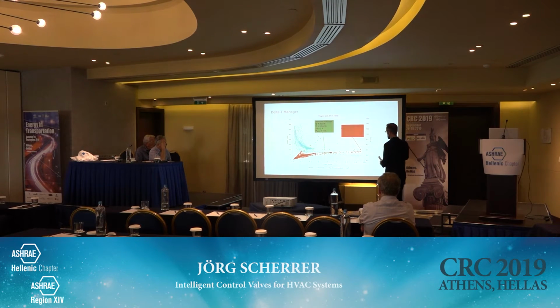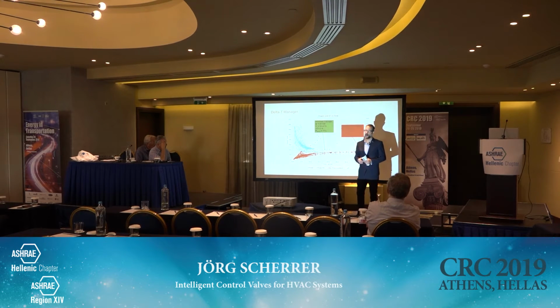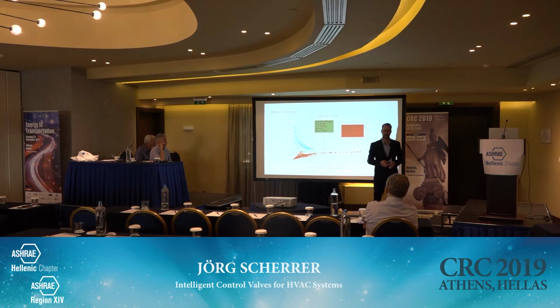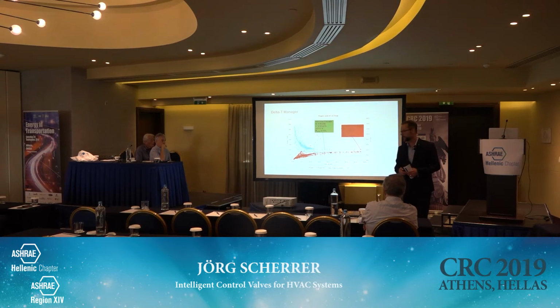I have less flow rate and I have a higher differential temperature. See here we are with 2 Kelvin, and here we have a differential temperature of 3 Kelvin. This is an effect when we have an intelligent control valve with delta T management. So all this area here on the right side we can avoid, and I can save energy on the pump side.